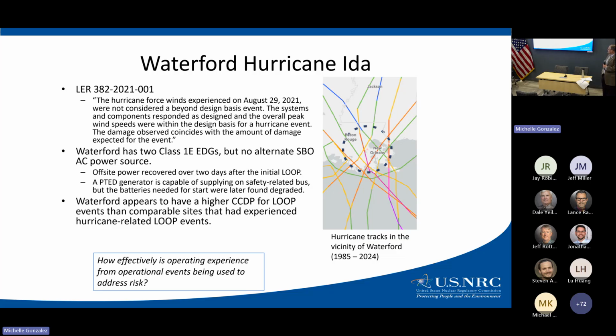What's interesting about Waterford is it does have what appears to be a higher CCDP for loss of offsite power events than what we see for comparable sites that also can experience hurricane-related loops. There is what they call a PTED generator capable of supplying backup power for the diesel generators, but during this event they didn't need it. They later found out the starting batteries for that particular diesel were degraded - believed it could start it, but they had not been fully charged prior to the event. So this really goes to looking at operating experience: are we learning from it, and what can be done to further ensure that we don't get into risk significant operational events.